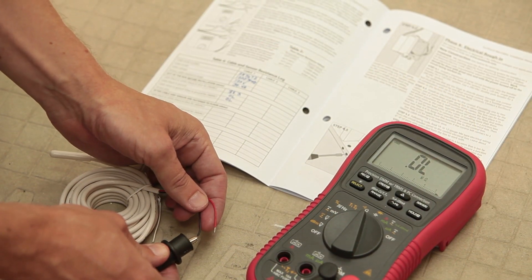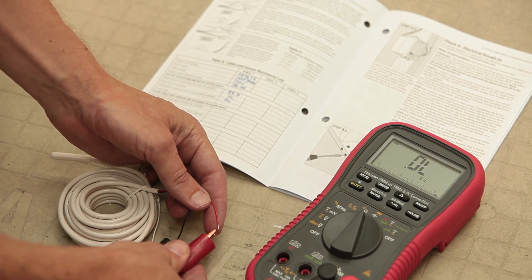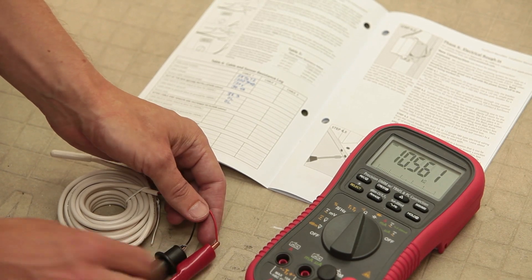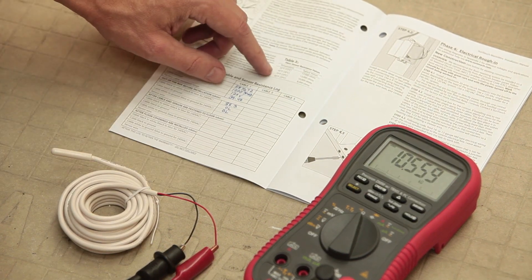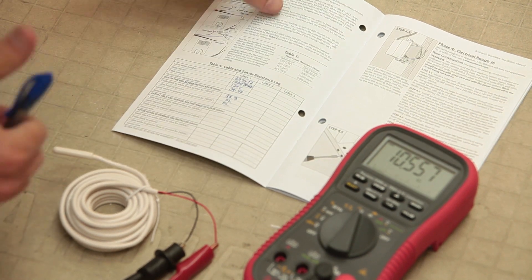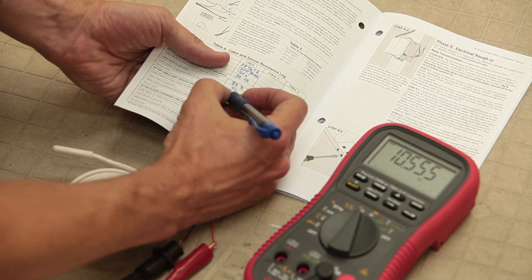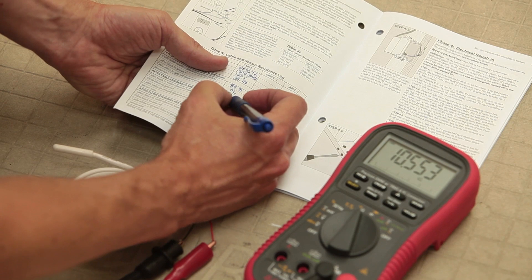Change the meter to the 20,000 ohm range to test the sensor wires. Place a test lead on each wire. Look up the resistance in the floor sensor resistance chart from the manual to see if the number is appropriate for the temperature in the space where you're testing.